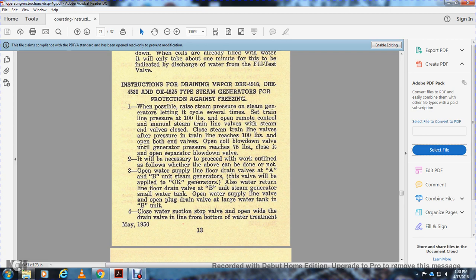When possible, raise steam pressure for the steam generator, letting the unit cycle several times. Set the train line pressure to 100 pounds with the remote control panel. After the train line pressure reaches 100 pounds, close the steam train line valve. Open both of the valves. Open the coil blow down valve with the generator pressure at 75 pounds. Close it and open the separator blow down valve.